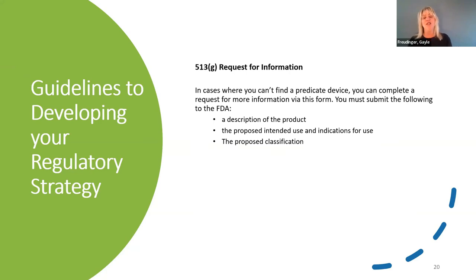So you might say something like, does the FDA agree with our determination of class two based on this, this, and this? You're basically asking them a question about where you think your device is classified and mentioning some of the issues you're struggling with, like you can't find a predicate device, what would be your guidelines or route for submission? The FDA will respond to you within 60 days, addressing whether the product is considered a medical device, and if so, stating the classification for you, and whether it will be subject to any active regulation or enforcement discretion. This is a great opportunity to get feedback from the FDA, which is something we always recommend, rather than going down a rabbit hole in the wrong direction.